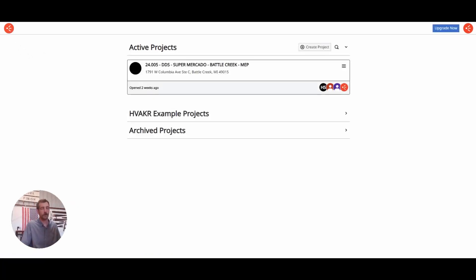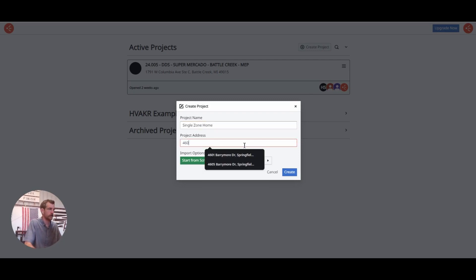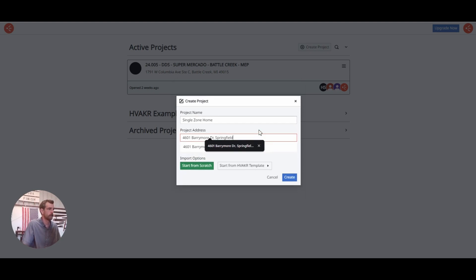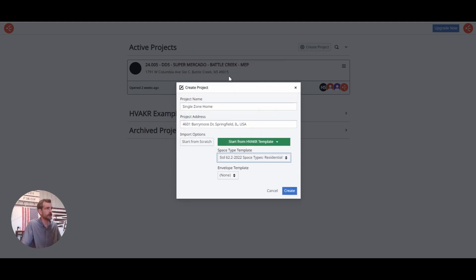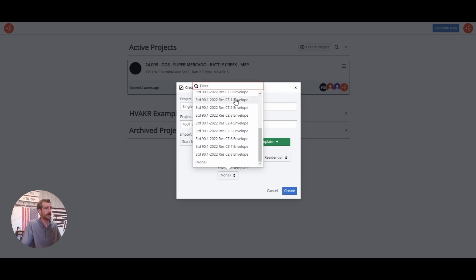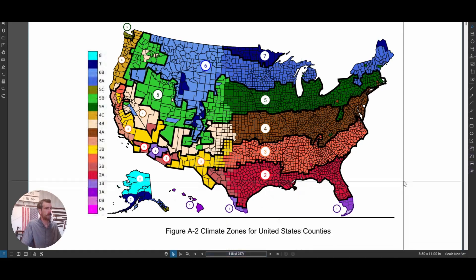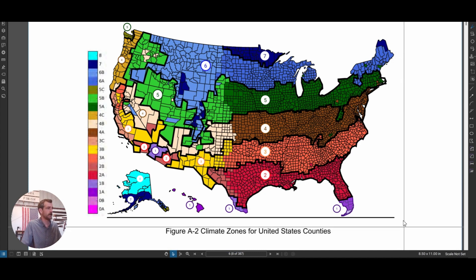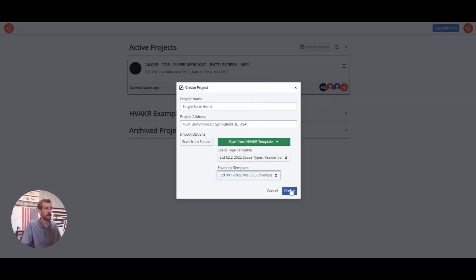This first project is going to be a simple single zone home. I'm going to create a project, name it 'single zone,' and put in my project address. I'm going to start from a template — space type is going to be residential. For envelope type, I need to determine my climate zone. Scroll down to the residential climate zones. If you don't know your climate zone, here's a map — this might be a good place to hit pause. I'm in Springfield, Illinois, which is climate zone 5, so I'll choose residential climate zone 5 and create.